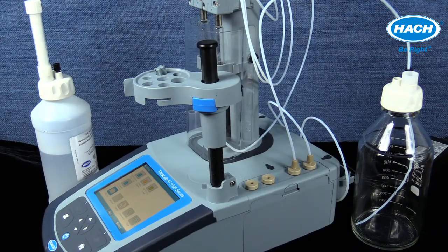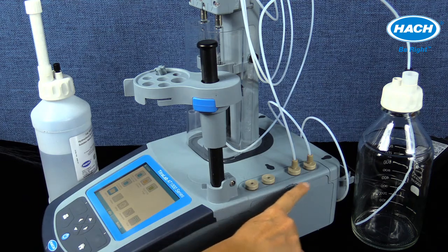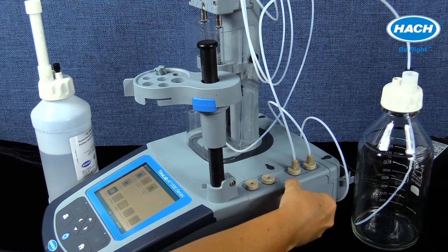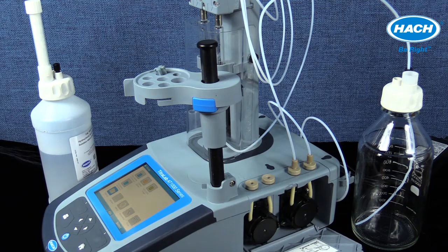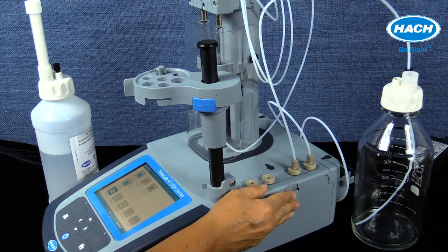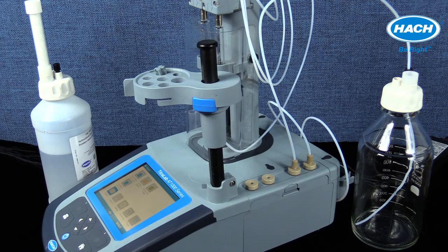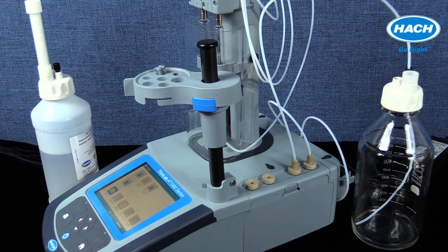The AT1000 series includes titrators with 1 or 2 pumps installed or with no pumps installed. The pumps are used to automatically deliver additional reagents that are required in the titration reaction and often buffer the sample. The reagents can be manually added when using a titrator without installed pumps and when the application software is edited from auto to manual addition. Purging the pump to remove old reagent and air bubbles is performed through the software. The software is also able to track or schedule maintenance or replacement of the pump components.